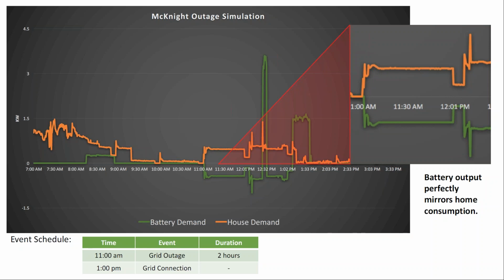The green line is what the battery is discharging during that same period. So I've kind of blown up that 2 hour section, and the two lines mirror each other perfectly, which is exactly what we want to see happen. We want the batteries to be matching what the house is consuming, which proves that it's doing exactly what it's designed to do.